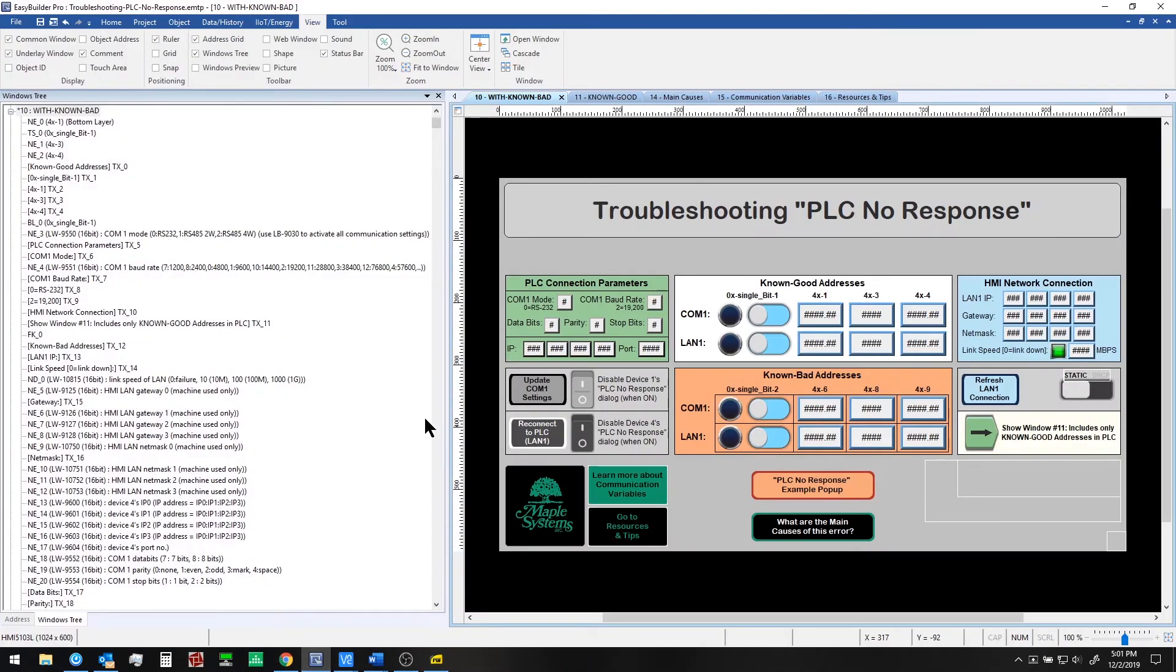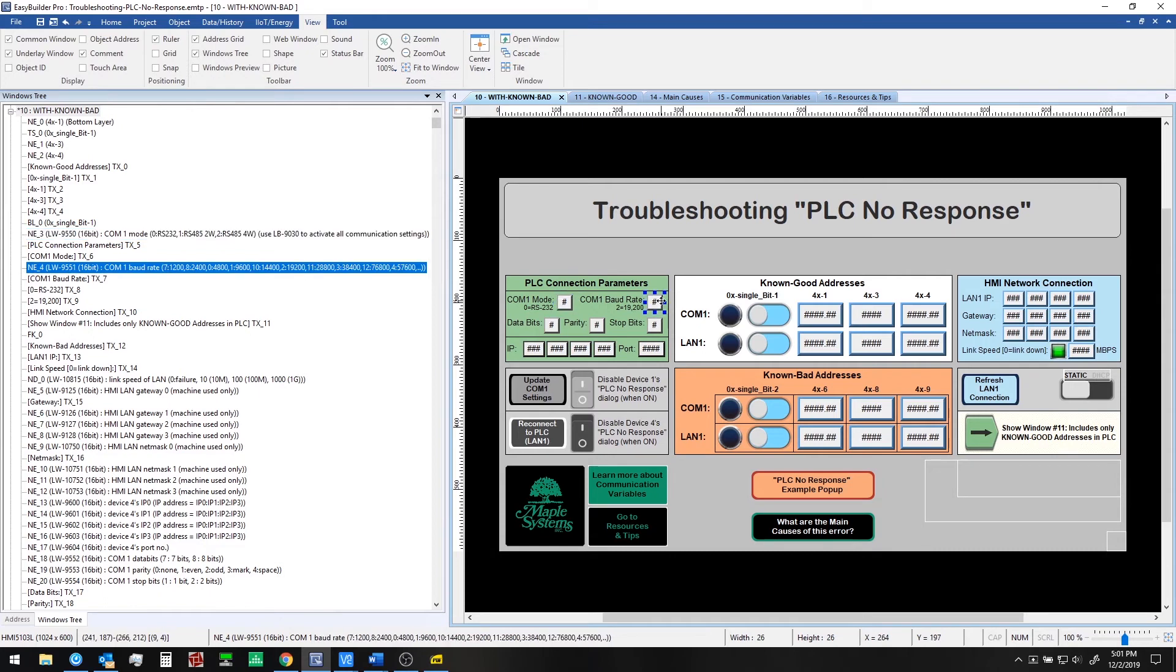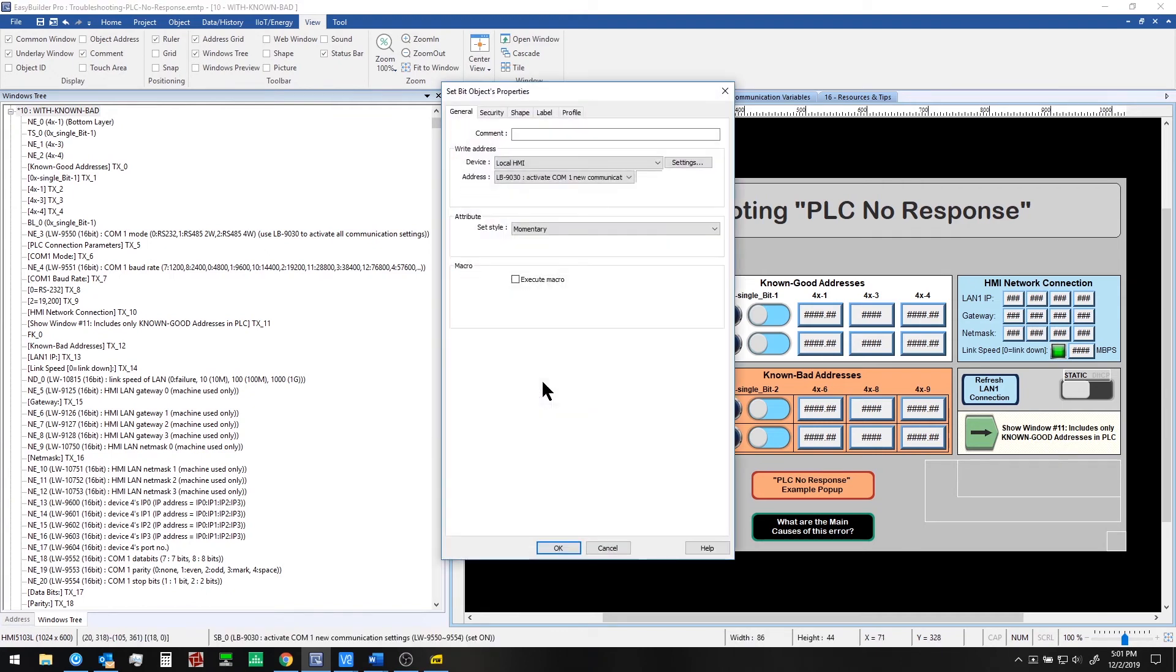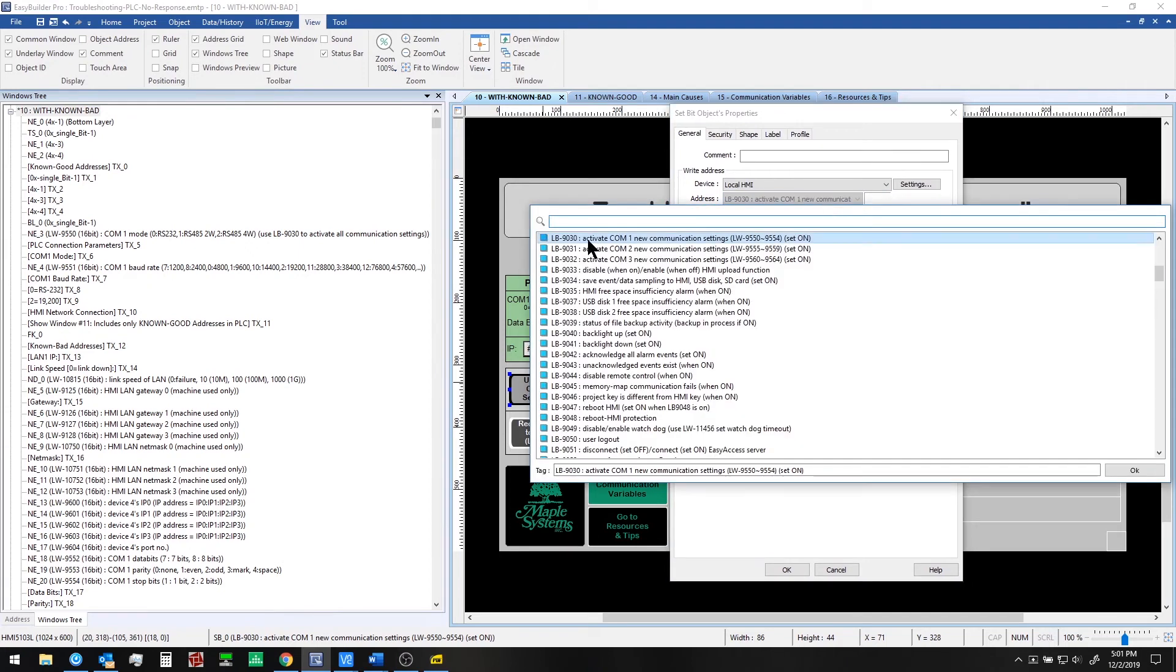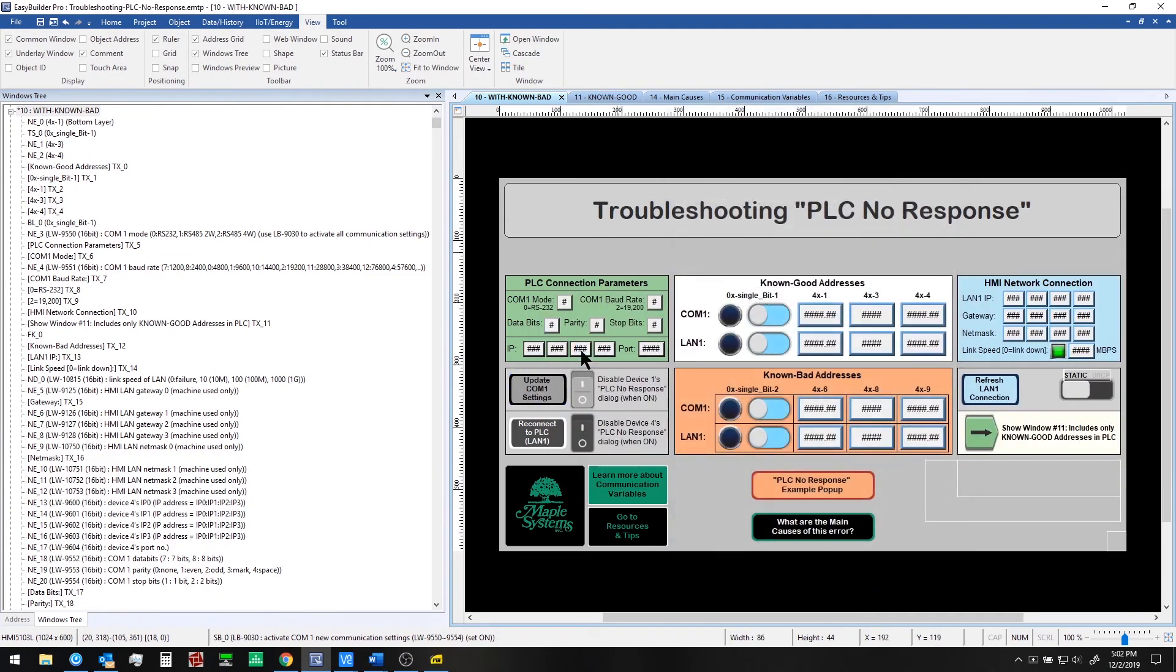Looking at the project in EB Pro for a given parameter we have sets of system registers that we can use. For example com1 mode is local word 9550. You can look through this project to explore the other ones that we have set up or look in the address tag library in EB Pro and you can even filter there for example baud rate you can type in baud and find the register that you need. If an operator enters a value into these registers then you will need a function to allow the new settings to be applied while the HMI is running. So with that you would set up a setbit object in this case local bit 9030 activate com1 new communication settings. So you set that on to update those.